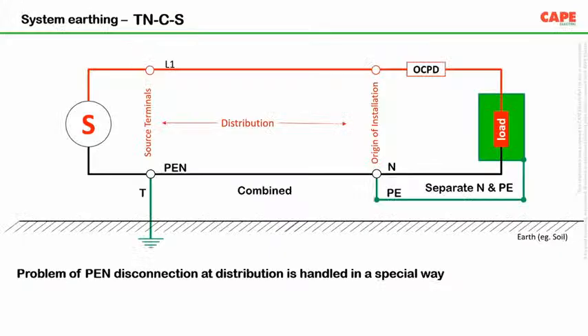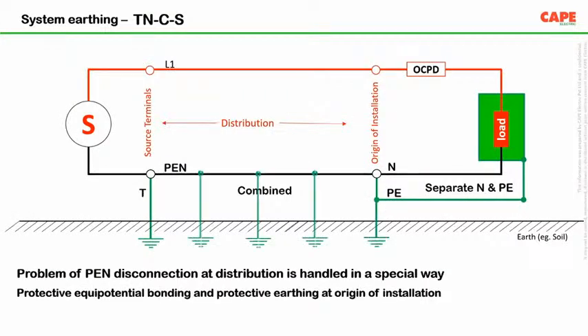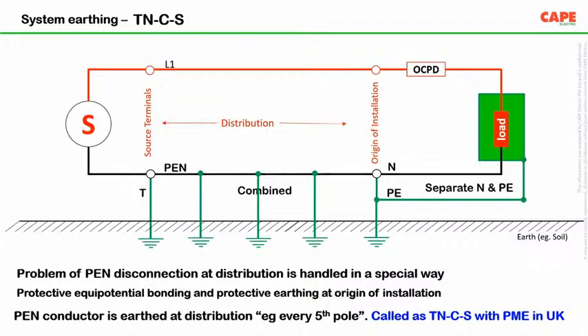Yeah, I will just show a slide. Now, what is written in the standard is to go for a TNCS system, where the transformer neutral is earthed. This conductor is called the combined neutral and protective earth conductor, the PEN conductor or CEN conductor. This particular conductor, along the post, maybe every kilometer 3 or 5 times, you are supposed to make this earthing, and this is the connection. Regulation 41, clause number 1 explains the neutral conductor shall be earthed by 2 separate and distinct connections.